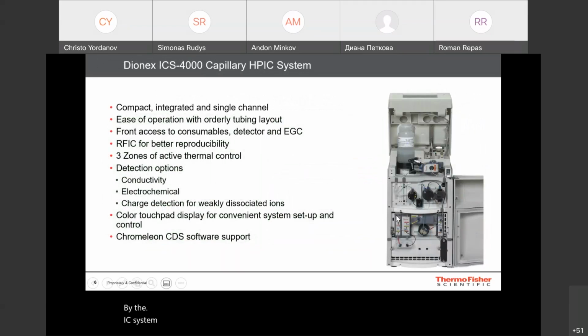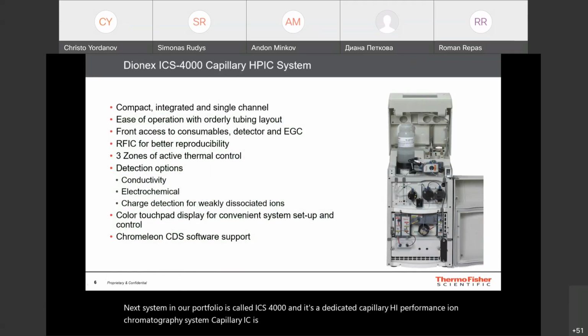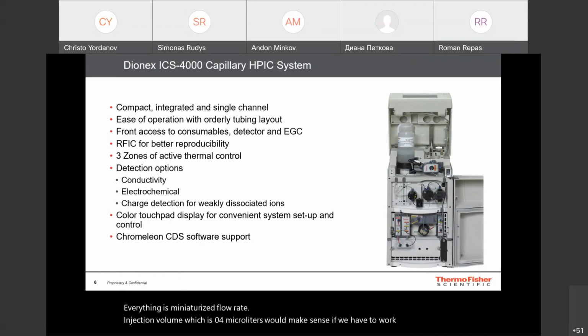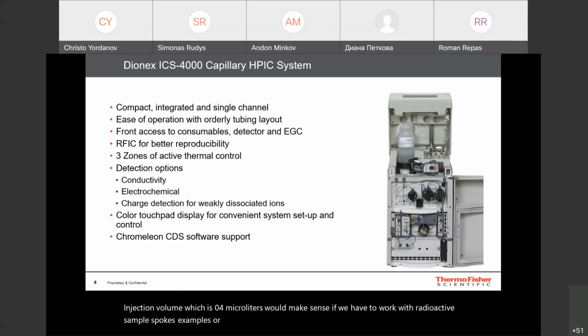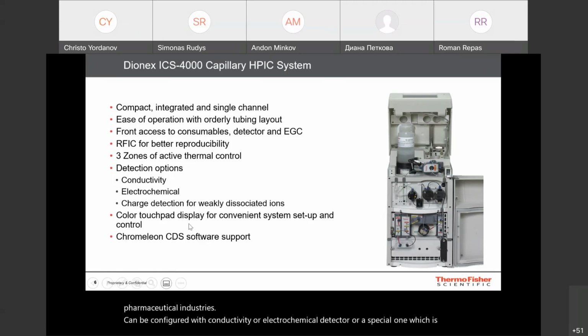system, like Integrion. The next system in our portfolio is called ICS 4000, and it's a dedicated capillary high-performance ion chromatography system. Capillary IC is a very special system. Everything is miniaturized. Flow rate, injection volume, which is 0.4 microliters, would make sense if we have to work with radioactive samples, toxic samples, or very rare samples like from R&D in some industries like the pharmaceutical industry. It can be configured with a conductivity or electrochemical detector, or a special one which is called a charge detector for weakly dissociated ions.